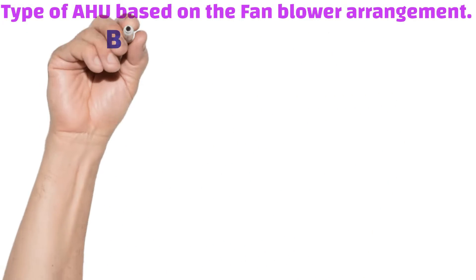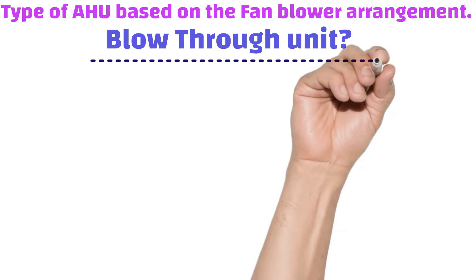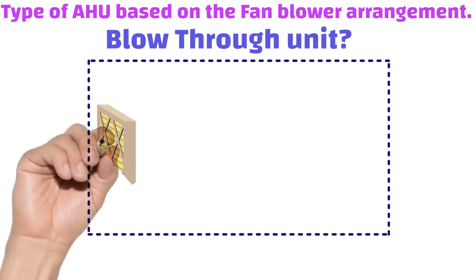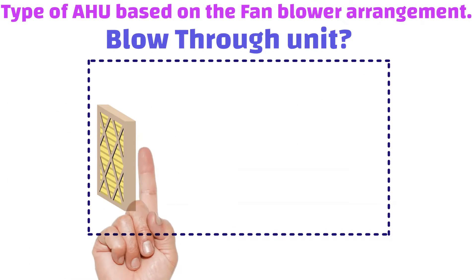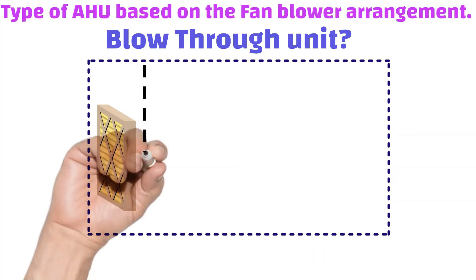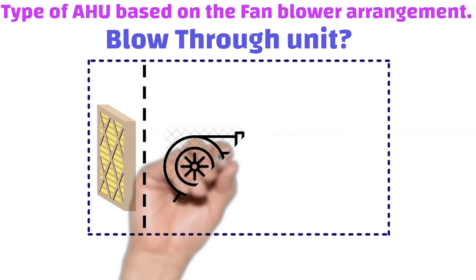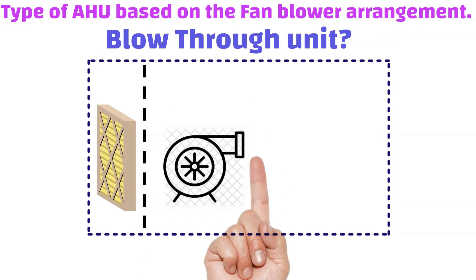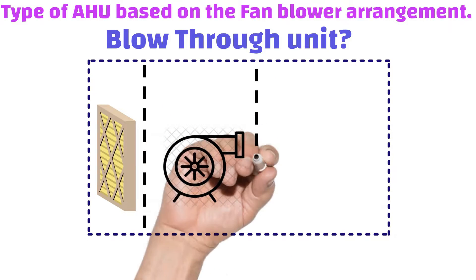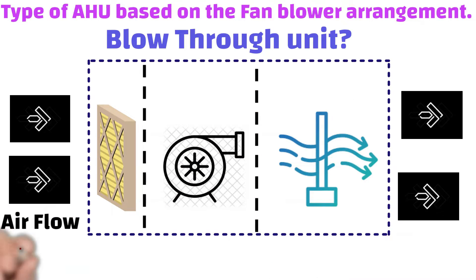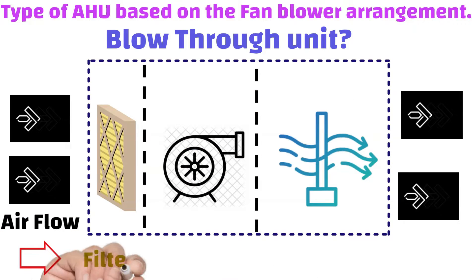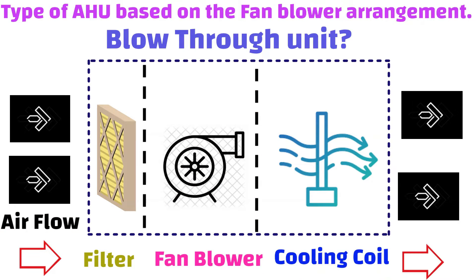First, we see about the blow through type of AHU based on the fan blower arrangement. The fan blower is located upstream of the unit, which is before the cooling coil, and this is called a blow through system. The fan blows the air through the cooling coil before discharging it to the space being conditioned or to the ducting system.